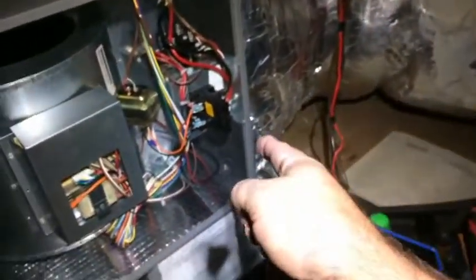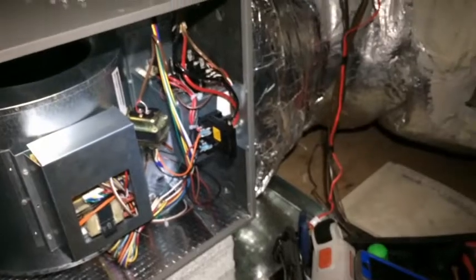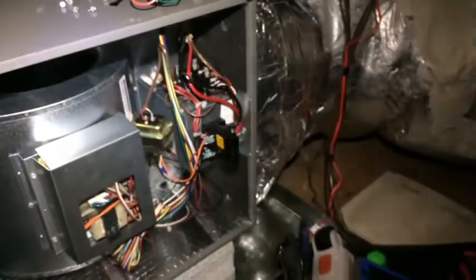So we have the power back on over here. Plugged a little plug-in in just so we could program the thermostats, because the thermostats are set up for an O reversing valve like we were talking about. I need to switch it to B, so we've done that. I can actually cut the power back off to this thing - just wanted to make sure that's all we had to do.